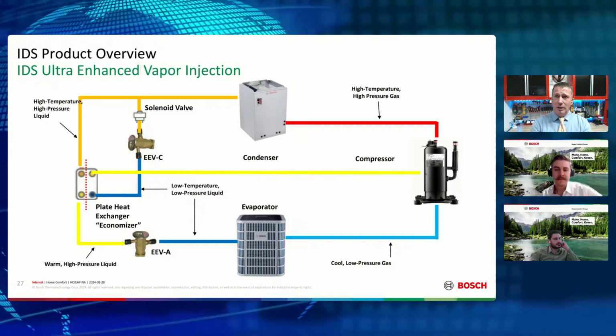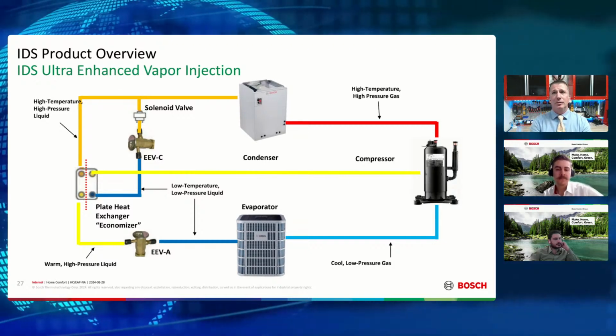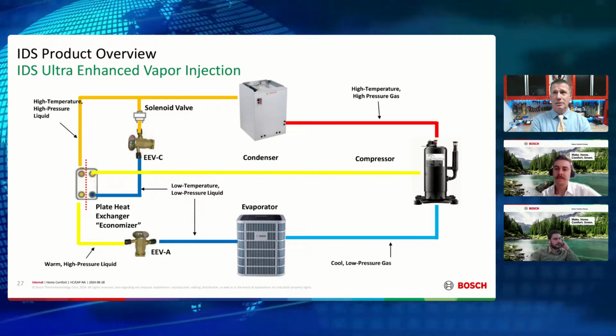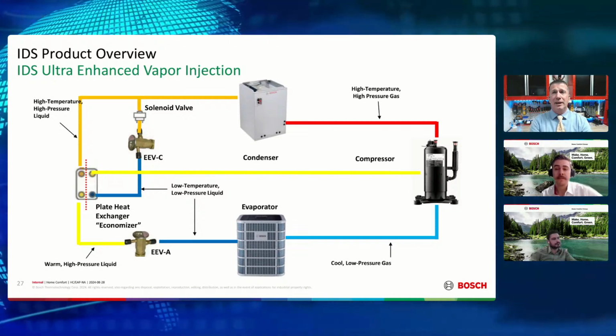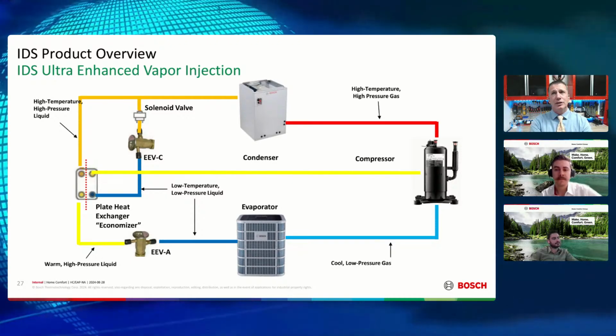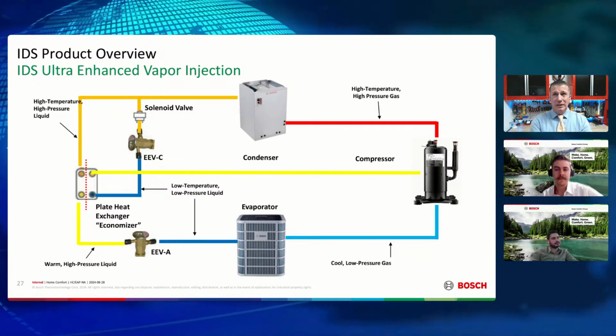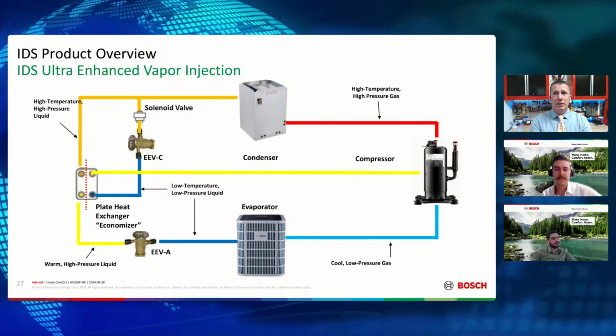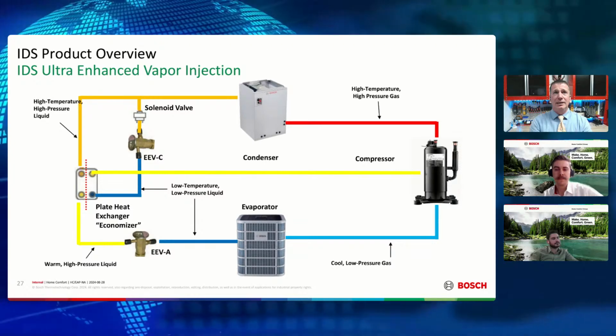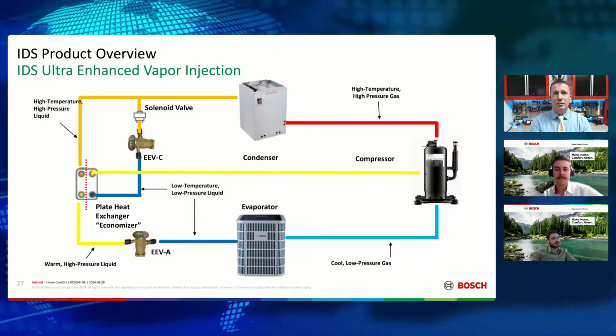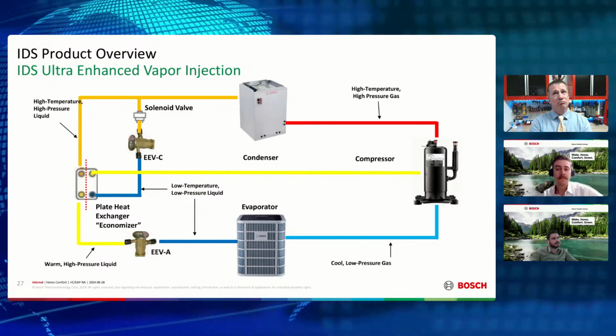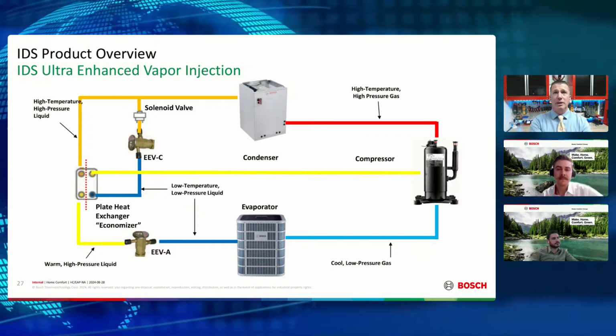We're going to have control algorithms monitoring things a little differently, but we're still just using pressure transducers and temperature thermistors, doing all the calculations in our control boards. So physically, we're really not overcomplicating the circuit - we're simply adding an additional refrigeration circuit within our network to bring some additional cooling back into our compressor.